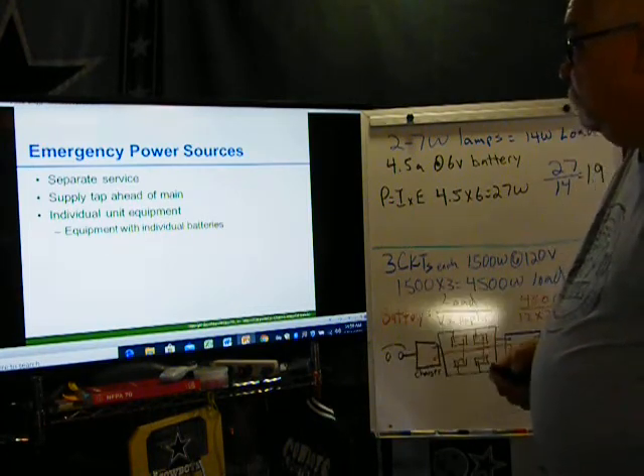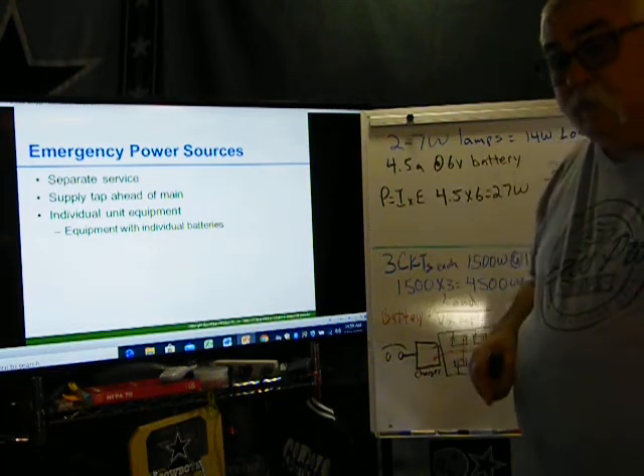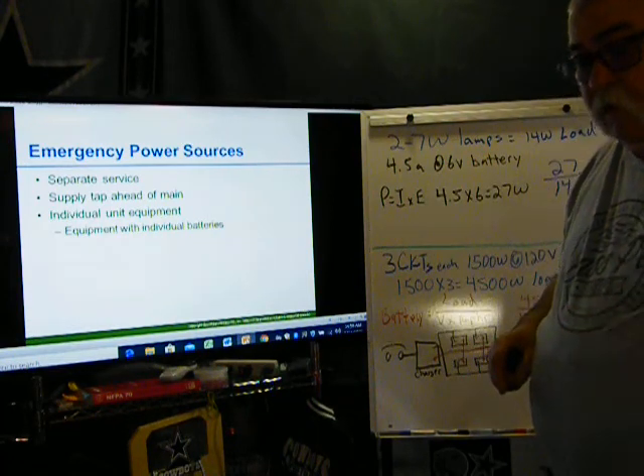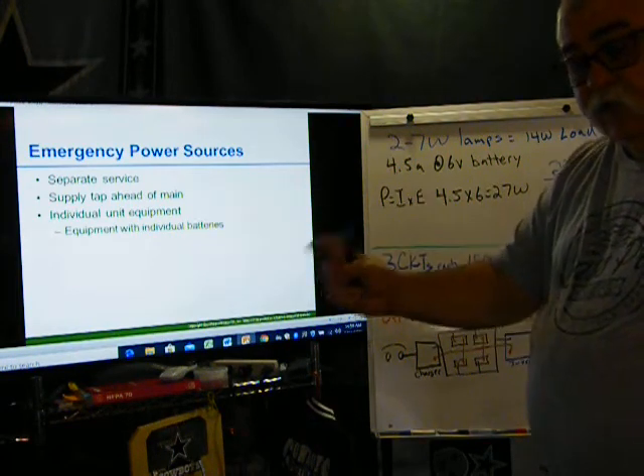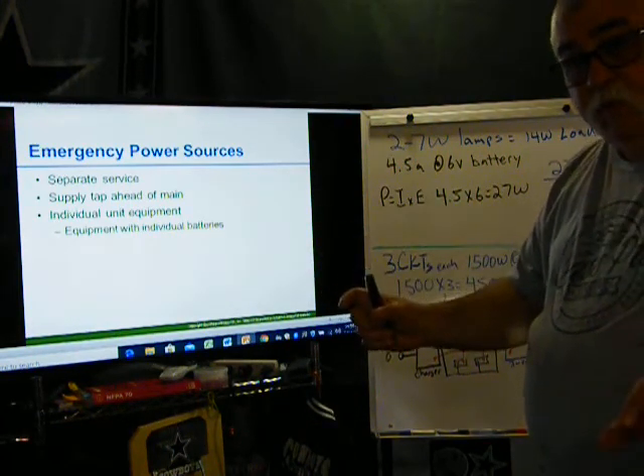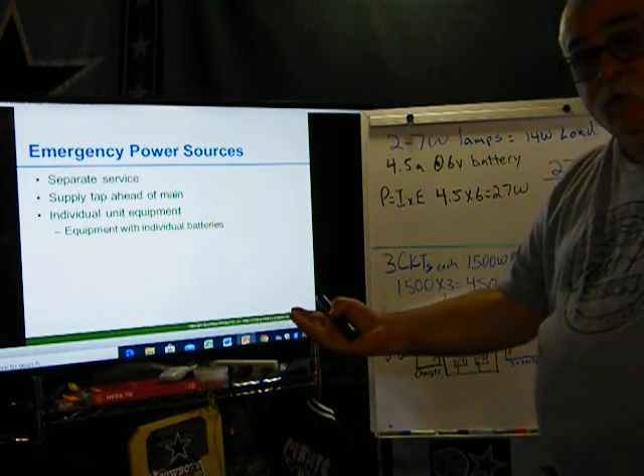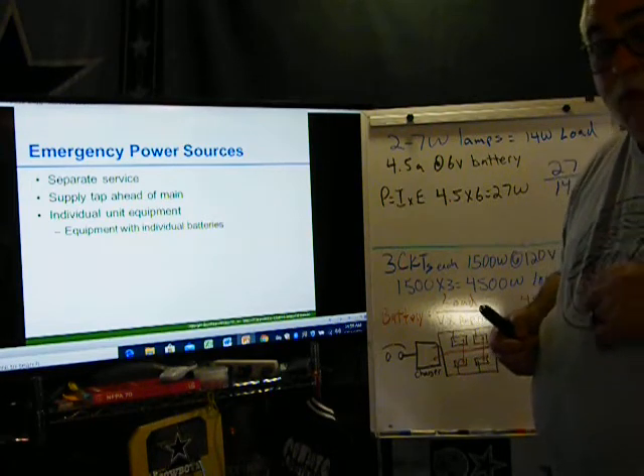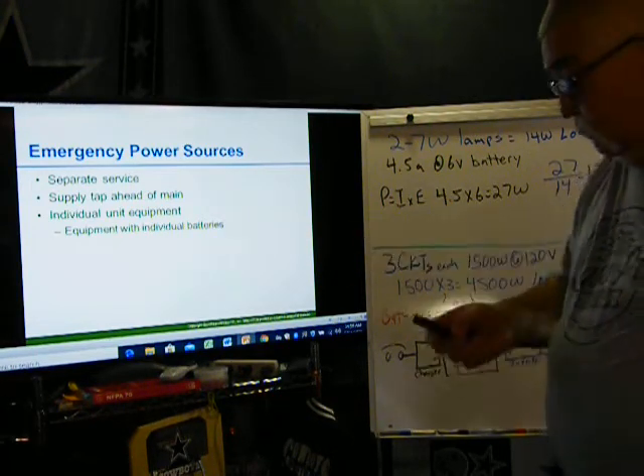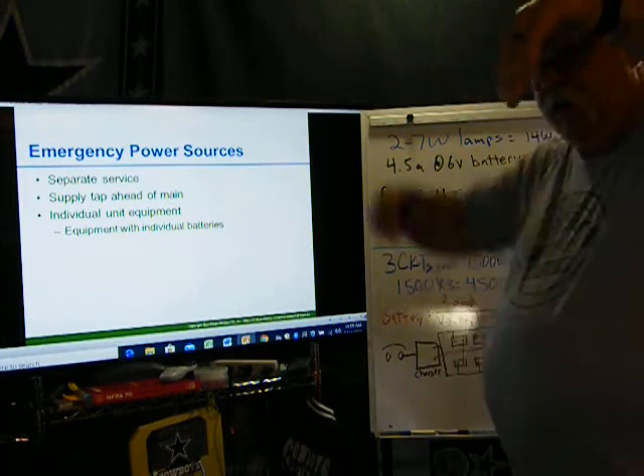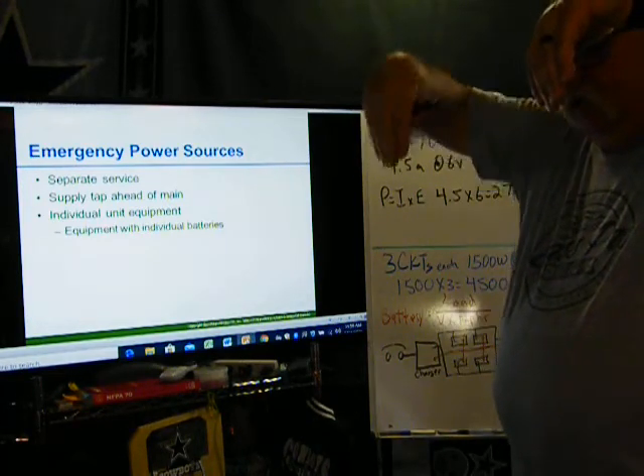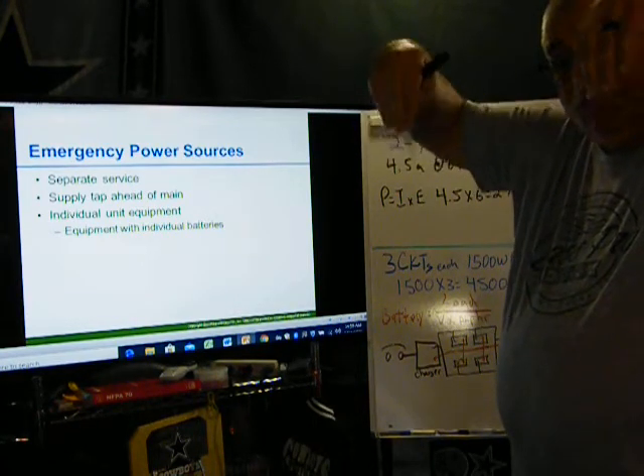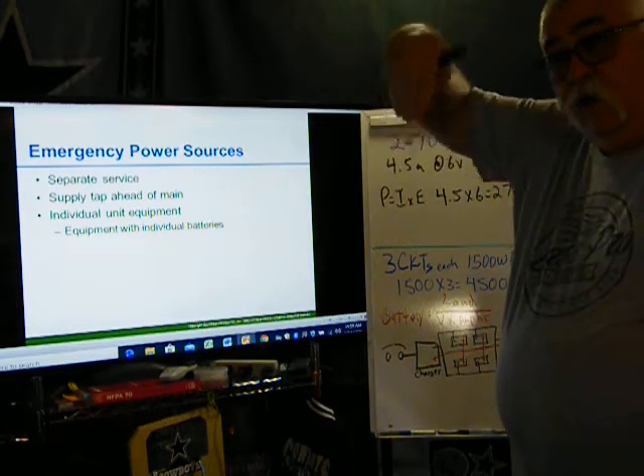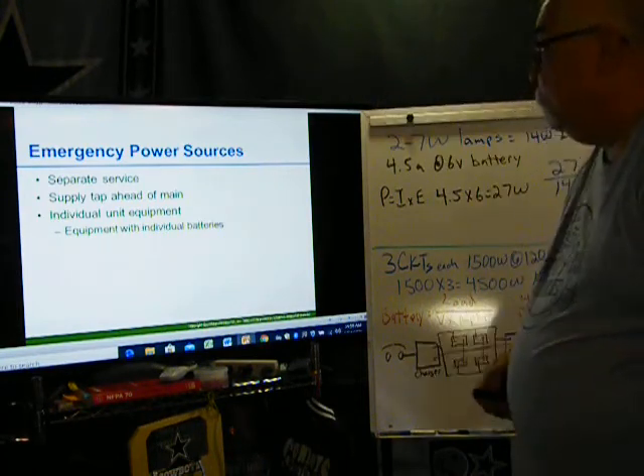Same thing with a supply tap ahead of the main. You're just bypassing where it goes to the main breaker and just adding a second main breaker. So if that main breaker goes bad, all you've got to do is transfer over to the next one, instead of having everything out while you change that breaker out. But again, if utility goes down, you're all done. Okay, so I've got a main breaker. It's always going through this one. If this one goes bad, it transfers over to this one. That gives me a chance to feed my building until I fix this one. Okay, that's all that does.